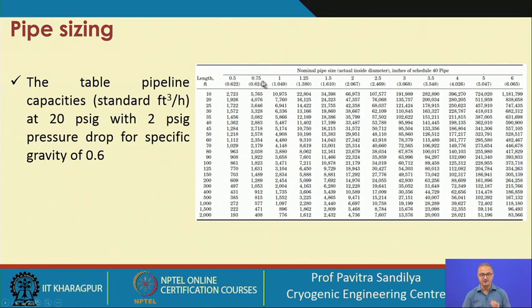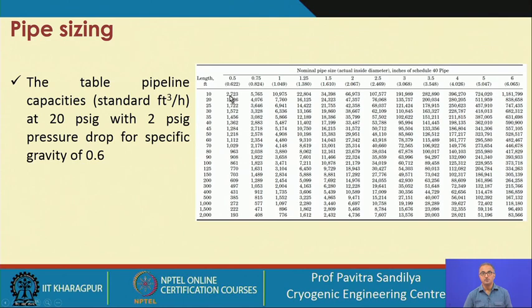The nominal pipe sizes of 0.5, 0.75, etc. are given, and with the calculated inside diameter from schedule 40, the capacities can be read. For example, a pipeline of 0.5-inch nominal diameter, schedule 40, has a capacity given in standard cubic feet per hour. This is how we find the allowable capacity for various pipe sizes.